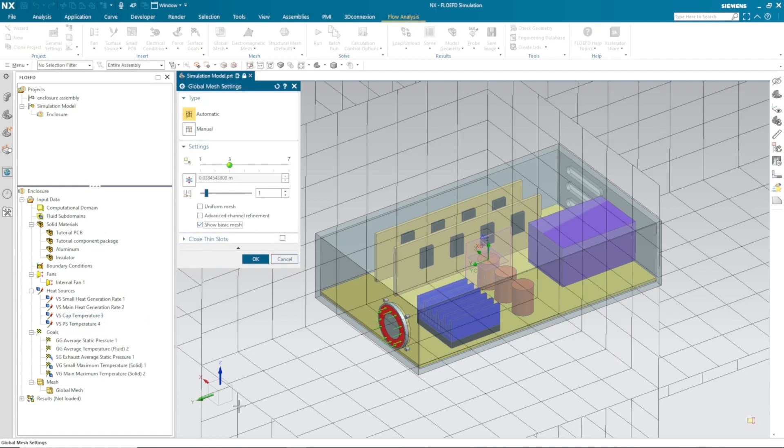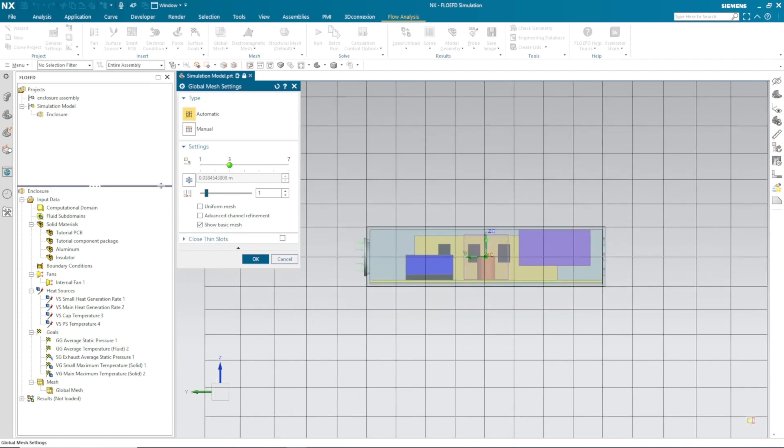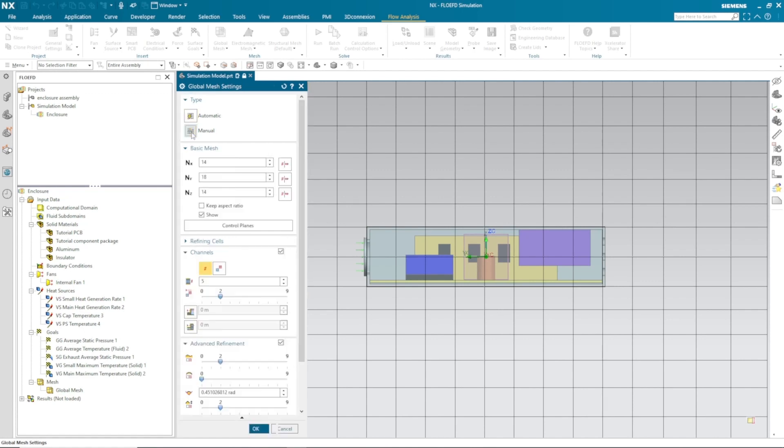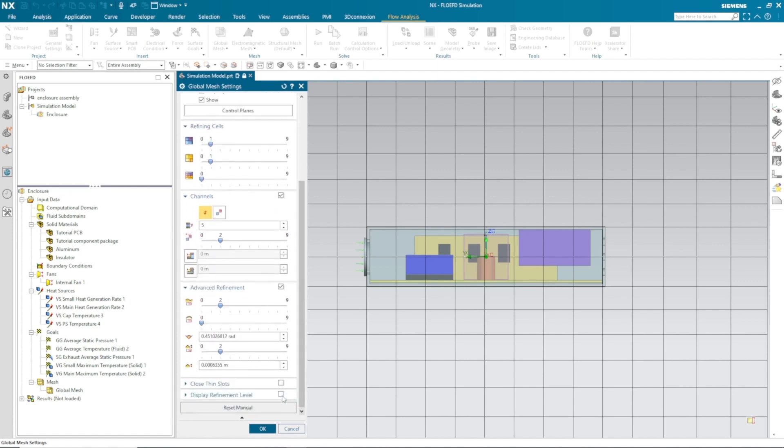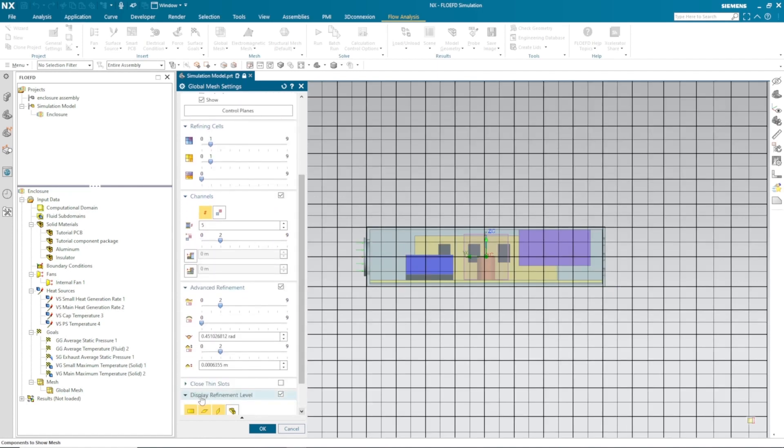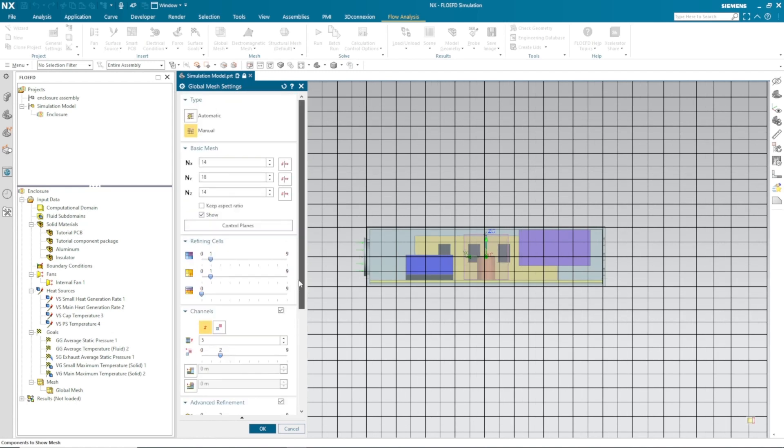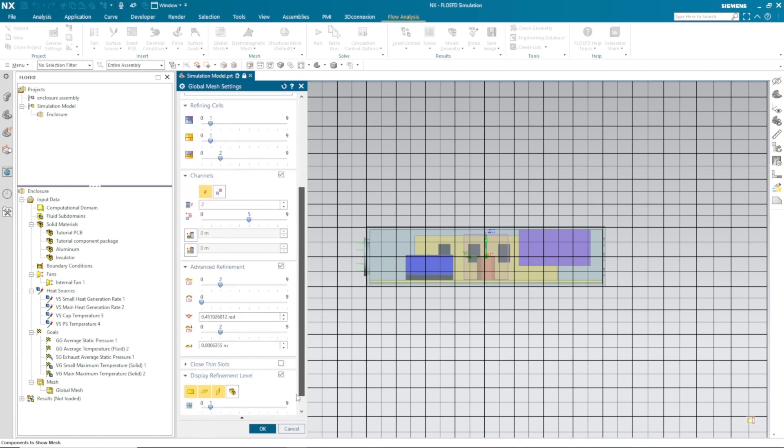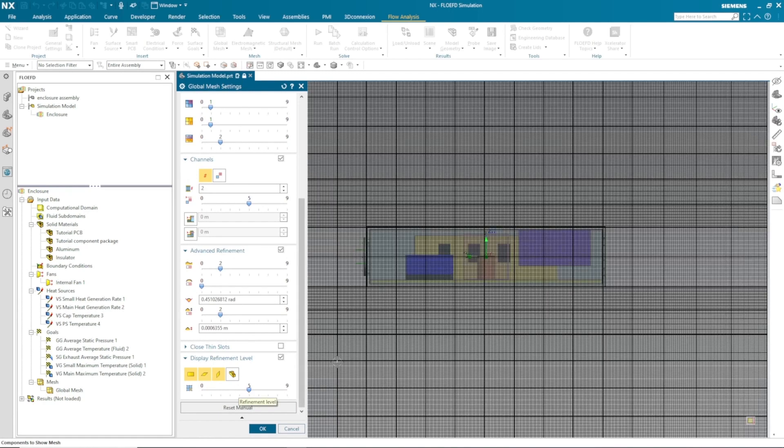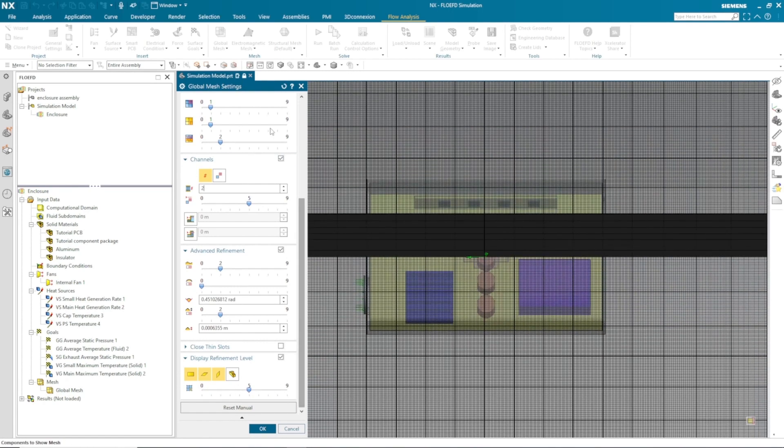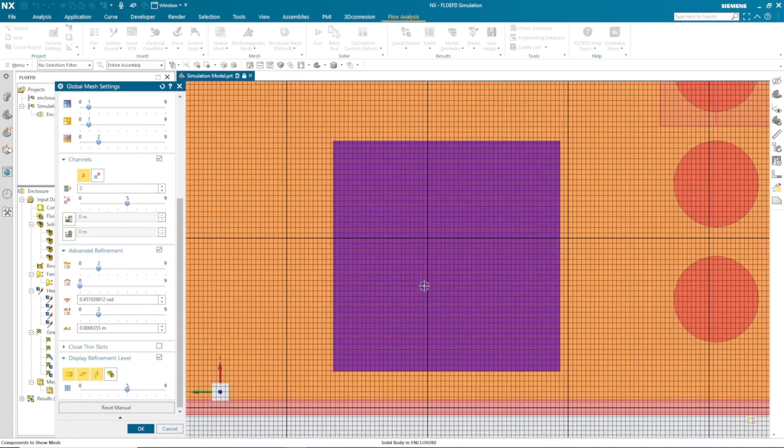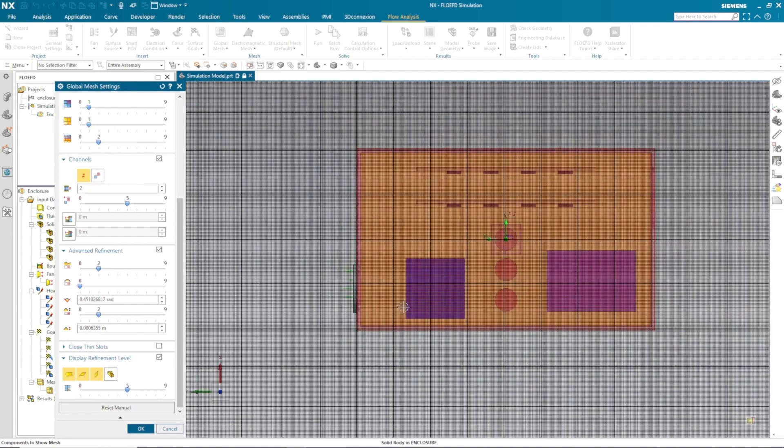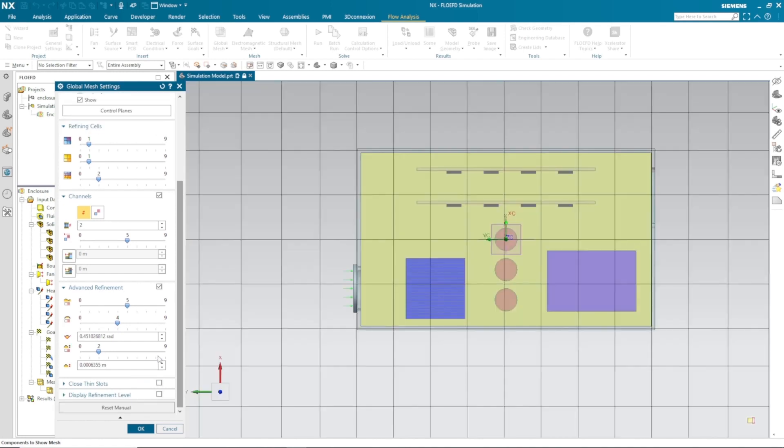Lastly, we need to create or define our mesh so it can capture all the thermal and flow details for our analysis. I need to define level one for my solid and fluid, and where our fluid is in contact with the solid, I need to define level two. I need at least two cells in a small or narrow channel, so I have to define the refinement level five and also adjust the advanced refinement parameters.